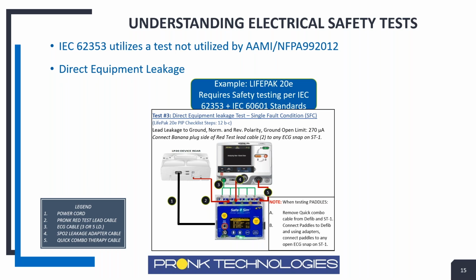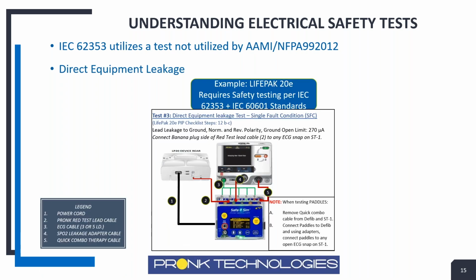So they want you to connect everything. Connect the ECG, connect the therapy cable, SpO2, connect your test lead to the chassis, and run a direct equipment leakage test. And the unique part about it is they have a very unique current limit. Under this condition, the current limit is 270 microamps. So very different from NFPA and the other standards. With the direct equipment leakage test, you're testing the leakage as a complete system and seeing what that pass-fail is. So I mention it because it's important always to look at that service manual and see what unique tests are required. All defibs are not designed to be performed to the same exact standards.